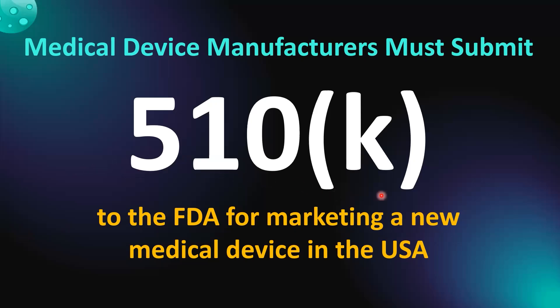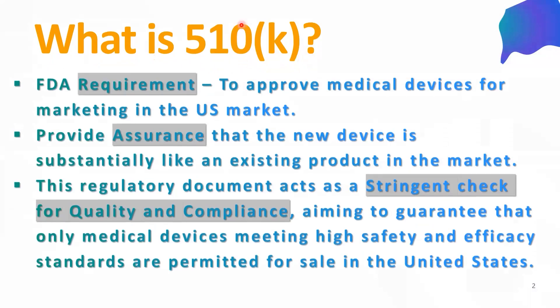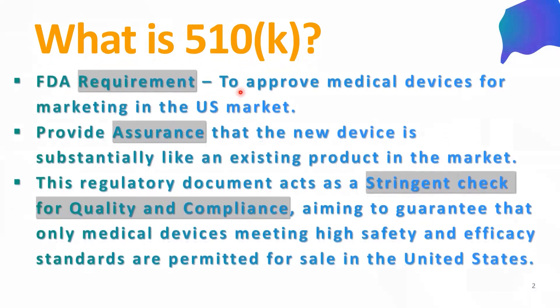The 510-K is a pre-market submission made to the U.S. Food and Drug Administration (FDA) to demonstrate that a device to be marketed is at least as safe and effective — that is, substantially equivalent — to a legally marketed device described as a predicate device. This process is named after Section 510-K of the U.S. Federal Food, Drug, and Cosmetic Act. Let's discuss a bit more about the 510-K, which is an FDA requirement to be fulfilled before marketing a medical device in the U.S. market.